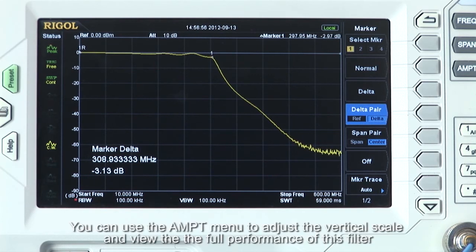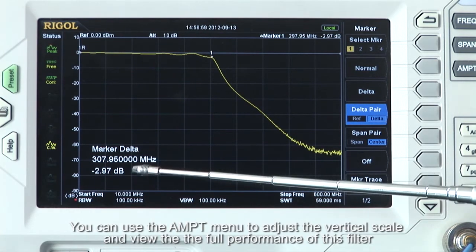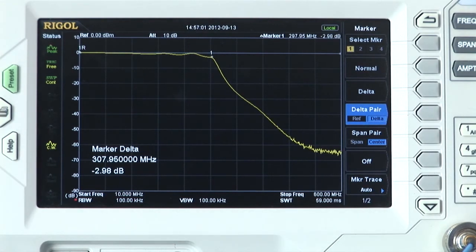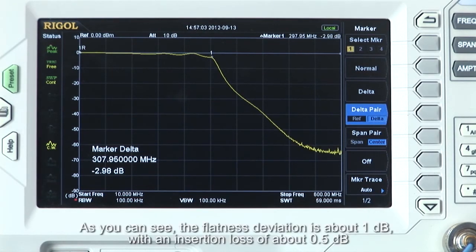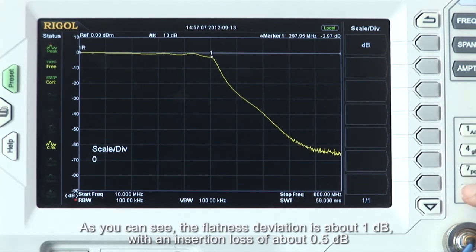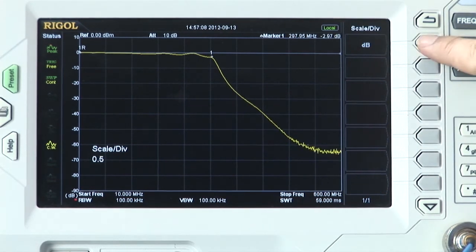You can use the amplitude menu to adjust the vertical scale and view the full performance of this filter. As you can see, the flatness deviation is about 1 dB with an insertion loss of half a dB.